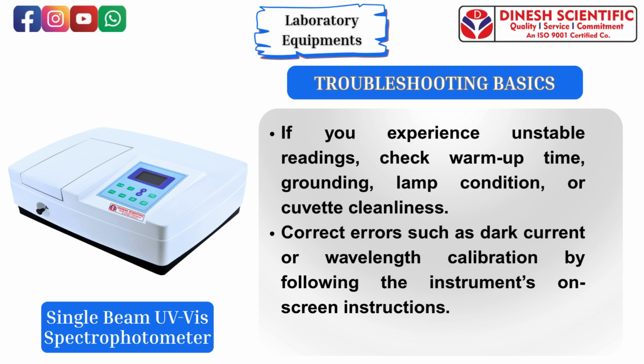Troubleshooting basics. If you experience unstable readings, check warm-up time, grounding, lamp condition, or cuvette cleanliness. Correct errors such as dark current or wavelength calibration by following the instrument's on-screen instructions.